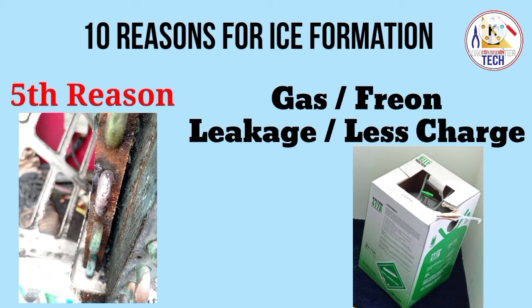To avoid ice formation from refrigerant issues, keep the refrigerant pressure normal. For R-410A refrigerant, the pressure should be around 110 to 115 PSI. Check the pressure according to the refrigerant type and there will be no ice formation in your indoor unit.